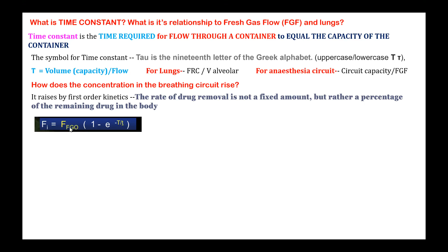Okay. So it is reached by first order kinetics. The rate of drug removal is not a fixed amount, but rather a percentage of the remaining drug in the body. So the inspired concentration will be FGO times (1 minus e to the power of minus t over the time constant). What does FGO mean? Fresh gas at the outlet. Okay? FGO is fresh gas at the outlet of the machine. So in this formula, it is inspired concentration, fresh gas concentration at the gas outlet, time, and the time constant. If you use this formula, then you will be able to decide what concentration you will be able to deliver to the patient. So what is the significance of the time constant in inhaled anesthetic use? Why do you have to break your head about this inhaled concentration?